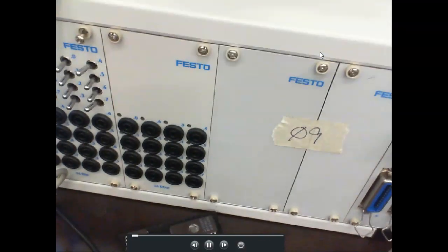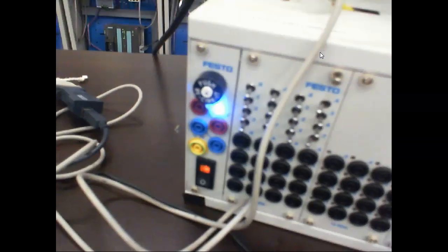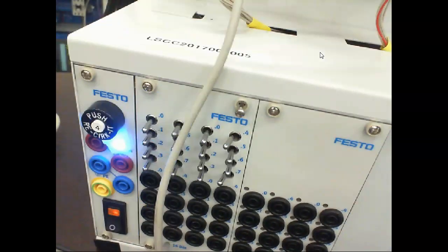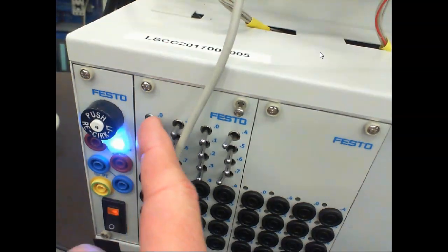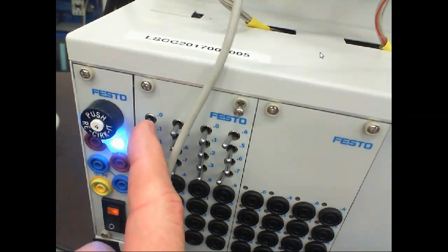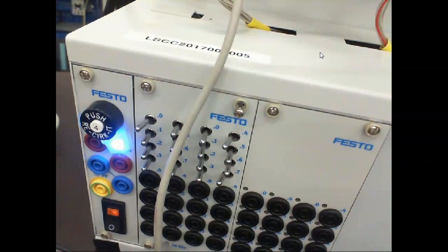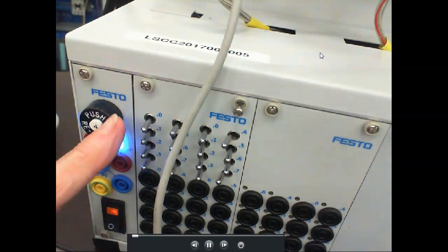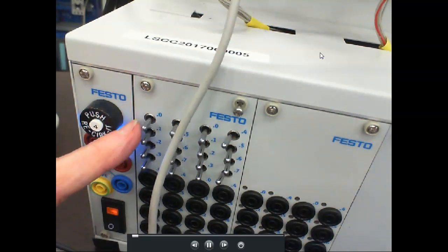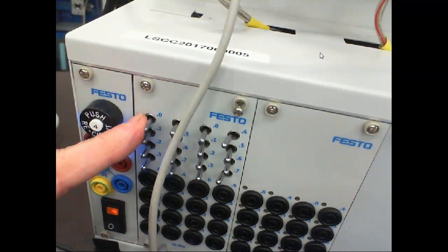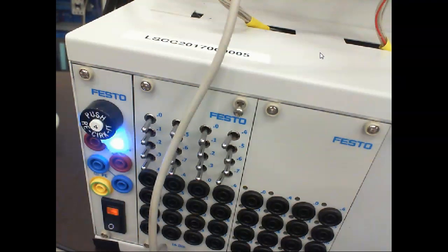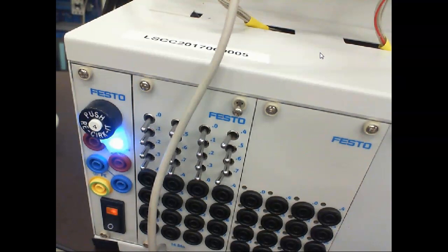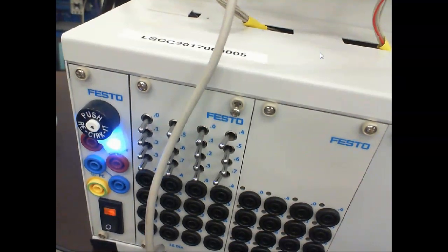We've got three positions, three things we can do with these switches. We can simulate. Right now in the center position, it's open. When I put it like that, it's permanently closed. Or we've got a momentary contact. We can push it to this side, and it acts like a momentary contact push button, which we'll use a lot.